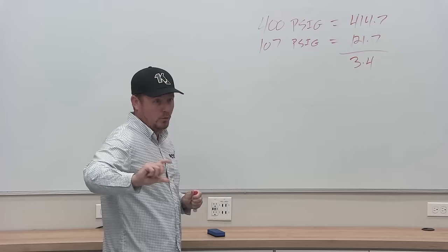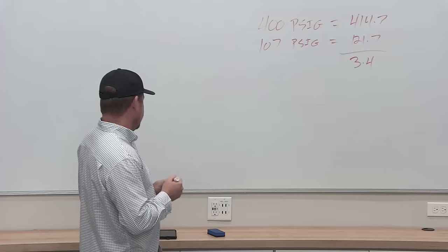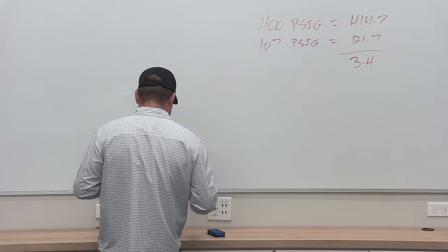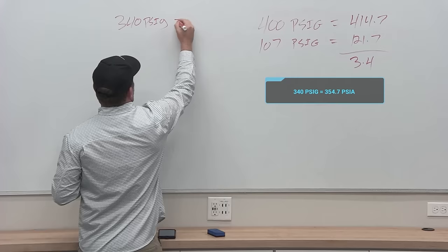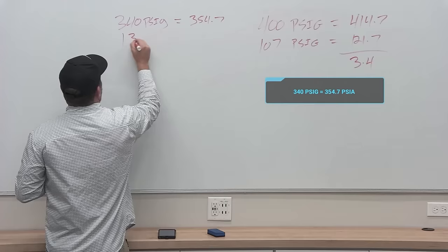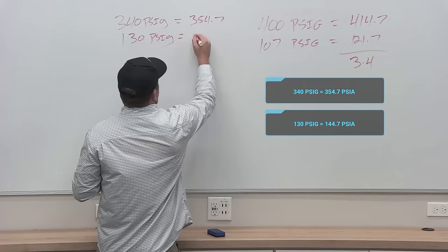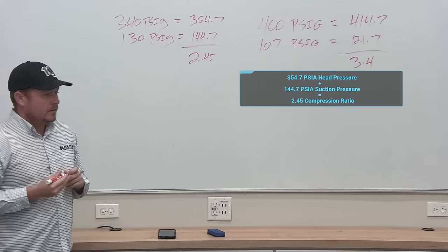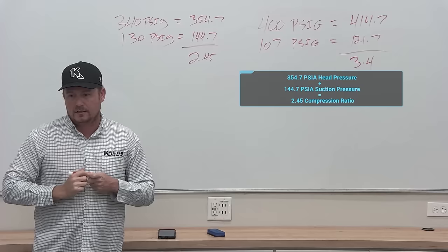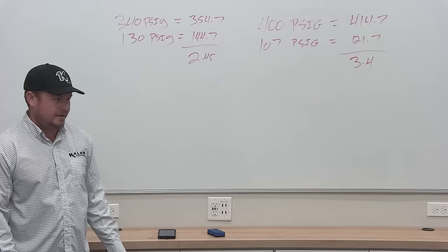On modern high efficiency systems at the edges of what you can see, you'd have 340 PSIG head — 354.7 PSIA — and 130 PSIG suction — 144.7 PSIA — giving a compression ratio of 2.45. With 2.3 being the lower limit you're generally going to see. If you start to get below that, that's actually a sign of a problem, which we'll talk about.